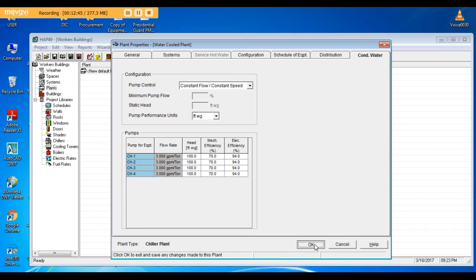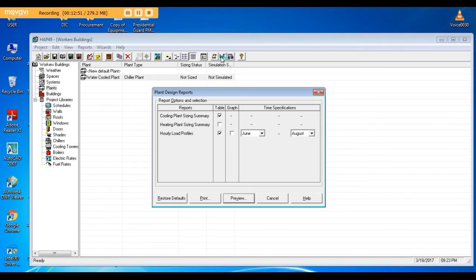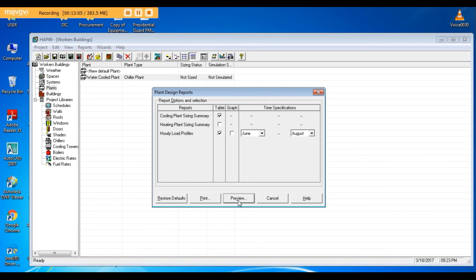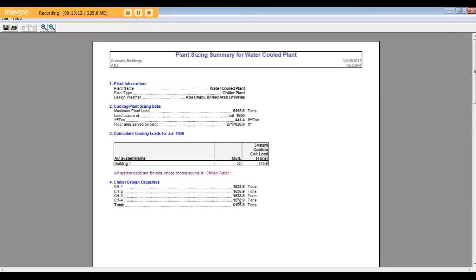Finished. Now let's go and do the sizing of this plant. I will do the sizing from June to August, the summer time. This will cover the peak load. So here our plant size is 6155 tons.